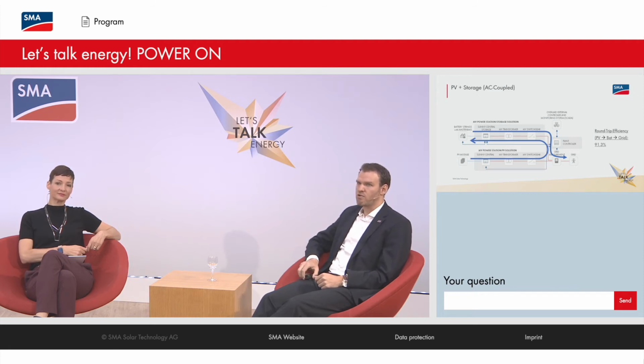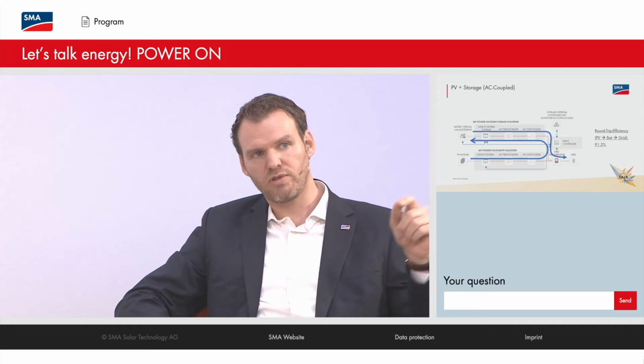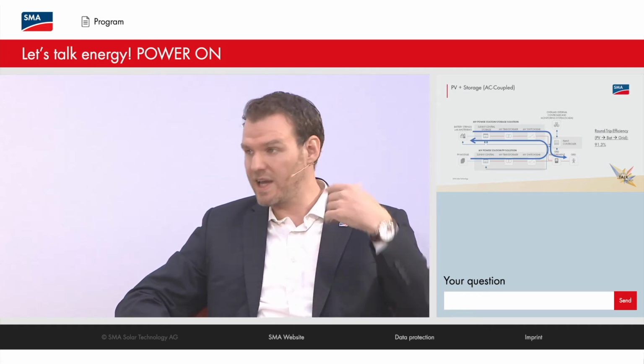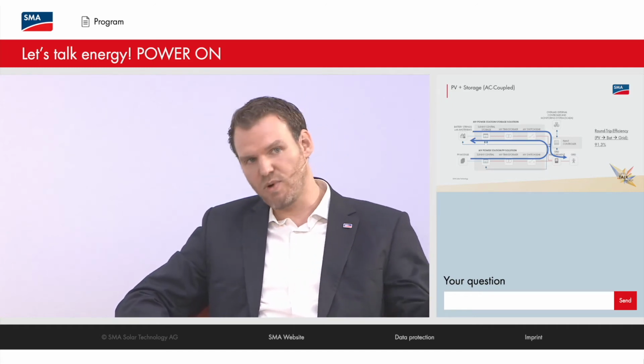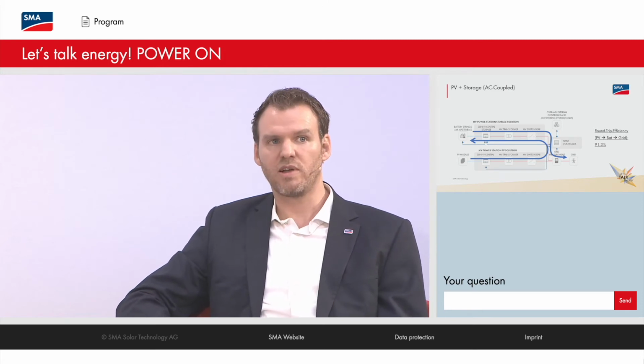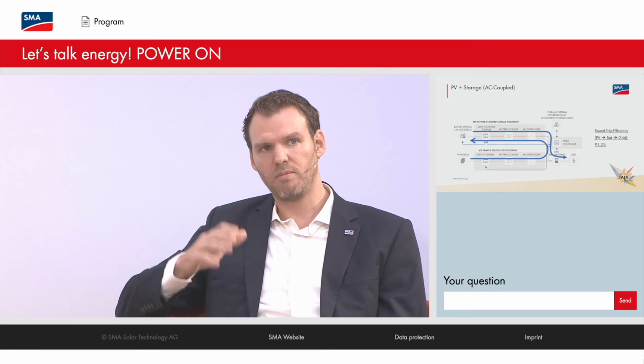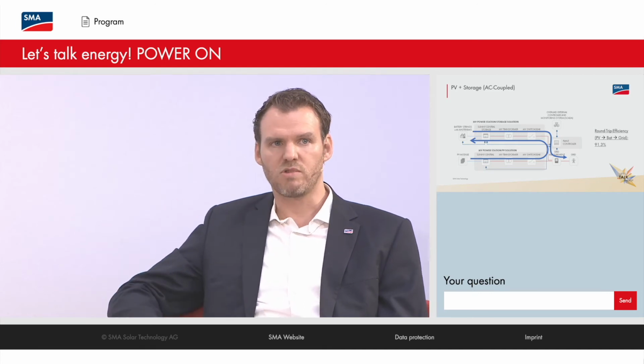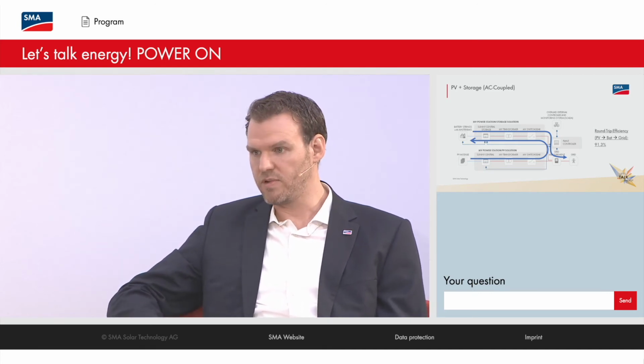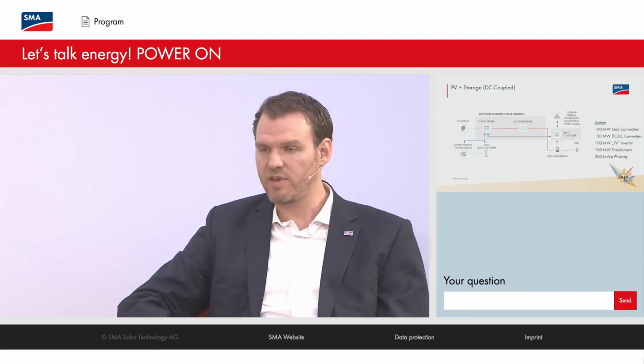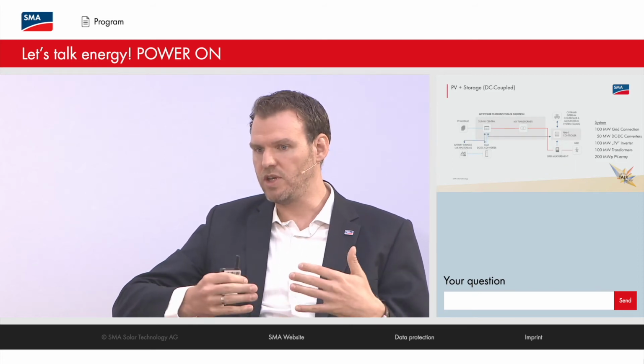And you have a certain round-trip efficiency. Obviously, you go from the solar panel through inverter, transformer, again transformer, inverter, and the way back to the network. So you see there's quite some losses in the system. So you have a round-trip efficiency from PV to battery to grid of roughly 91.3%. So more or less 8.7% of the yield is actually lost.